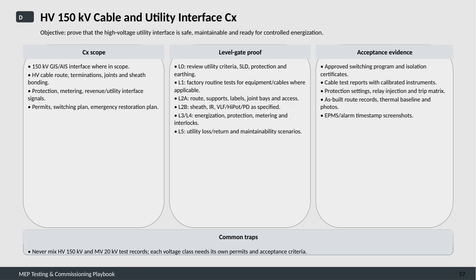maintainability scenarios. For acceptance evidence, it's critical to have approved switching programs and isolation certificates, detailed cable test reports using calibrated instruments, documented protection settings including relay injection and trip matrices, as-built route records with thermal baseline data and photos, and EPMS alarm timestamps to confirm operational readiness.